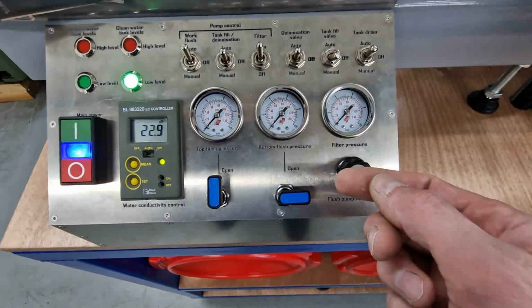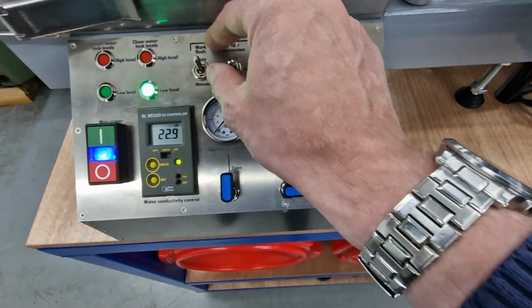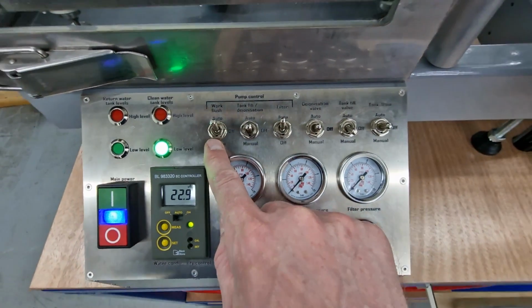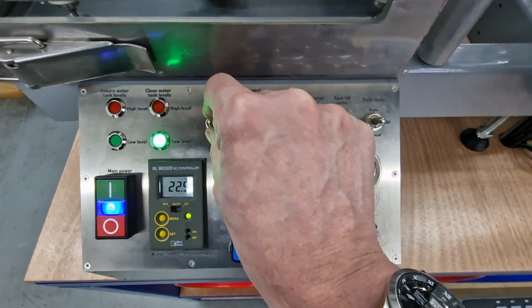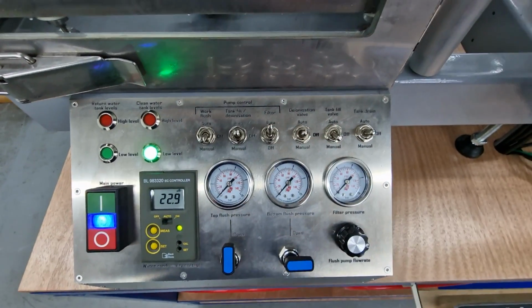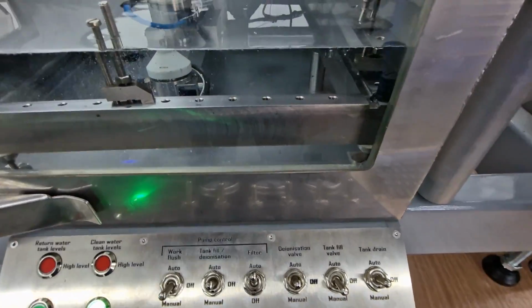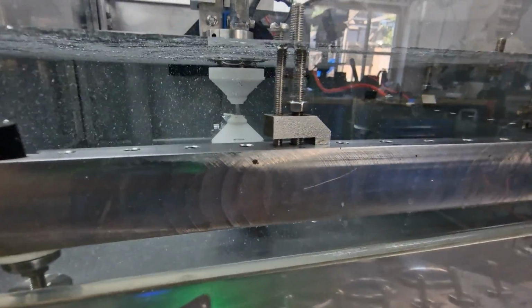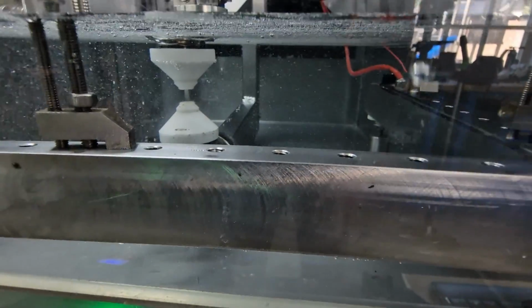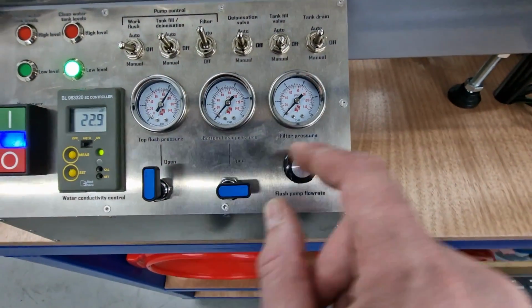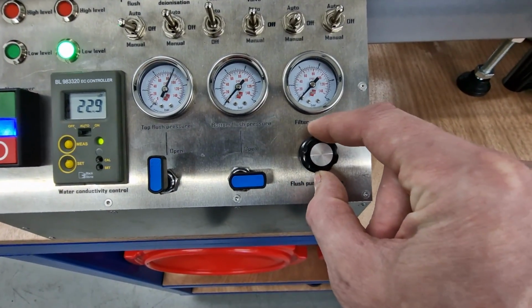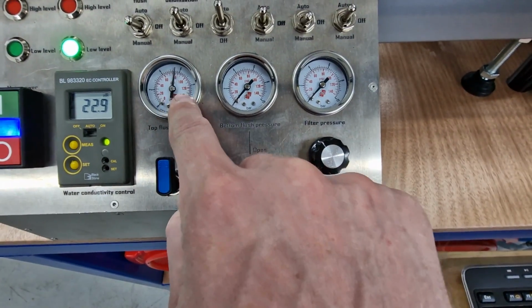Yeah, I can start flushing, for instance. So here's the flushing, it's now set to auto. For computer control, I can set it to manual. Now the pump ramps up. I can control the water pressure here, as you can see, this is the pressure through the flush cup.